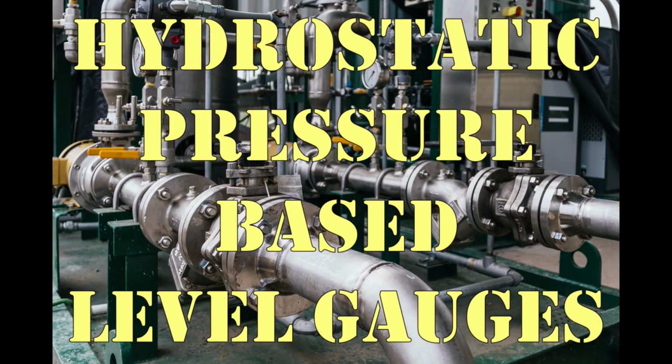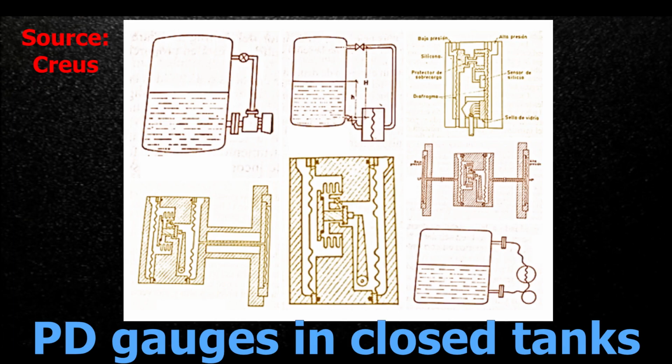Today I'm gonna talk about differential pressure. When the tank is closed and under pressure, a tube is connected to the upper part of the tank and the pressure difference between the upper and lower intake is measured using the transmitters that we can see in this image. This is because it is necessary to correct the indication of the device for the pressure exerted on the liquid. If the pressure is great, the measurement will not be exact.